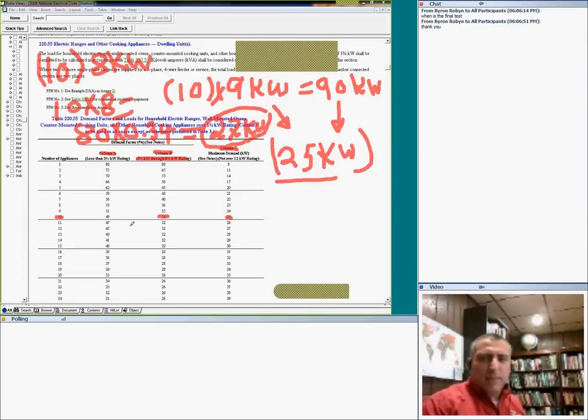Anybody has any question about that? The range calculation? Any question? The range calculation, guys, has a whole lot of issues. If they're all below 3.5 kW, then you apply this column. If they're all between 3.5 all the way to 8 3/4, you apply this column. If they're more than 8 3/4, you apply this column with some restrictions.